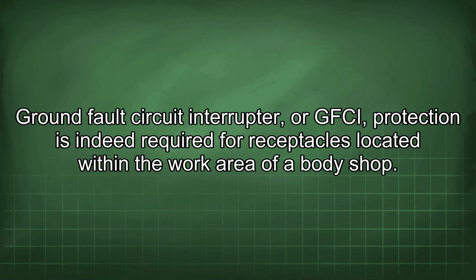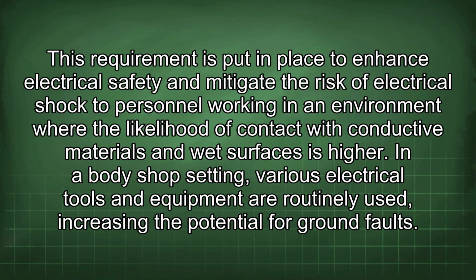Ground fault circuit interrupter, or GFCI, protection is indeed required for receptacles located within the work area of a body shop. This requirement is put in place to enhance electrical safety and mitigate the risk of electrical shock to personnel working in an environment where the likelihood of contact with conductive materials and wet surfaces is higher. In a body shop setting, various electrical tools and equipment are routinely used, increasing the potential for ground faults.